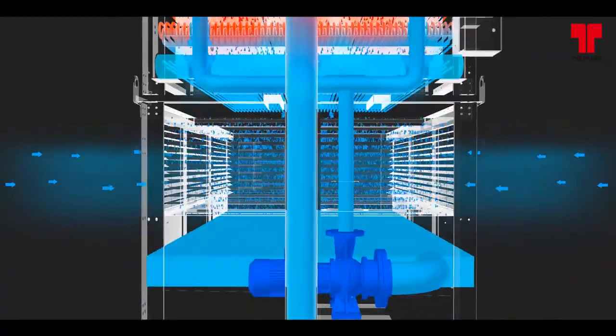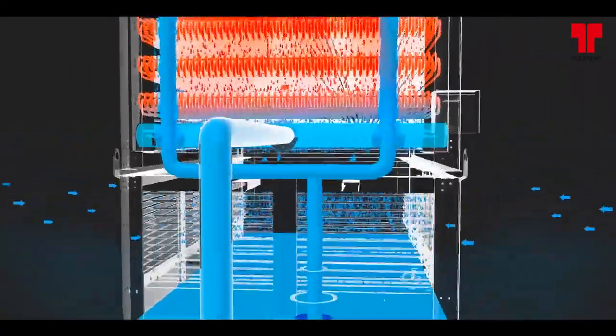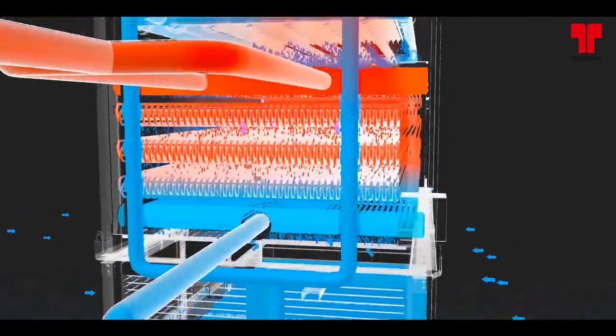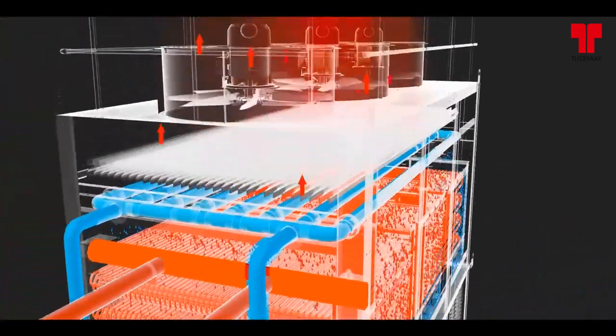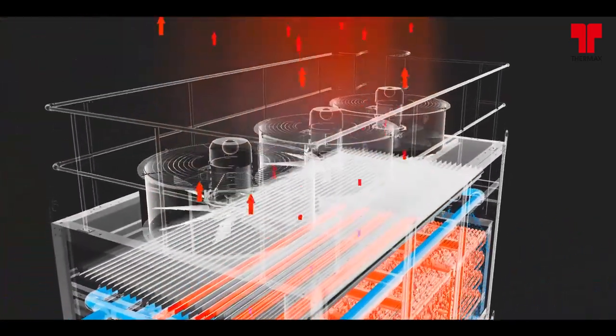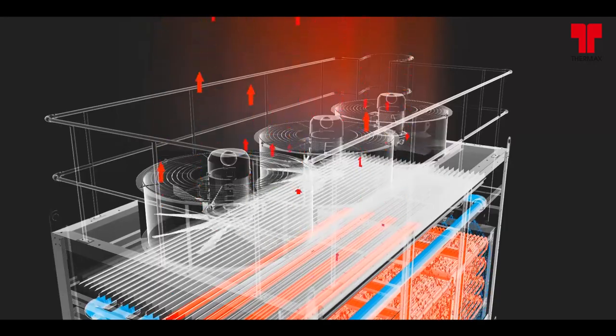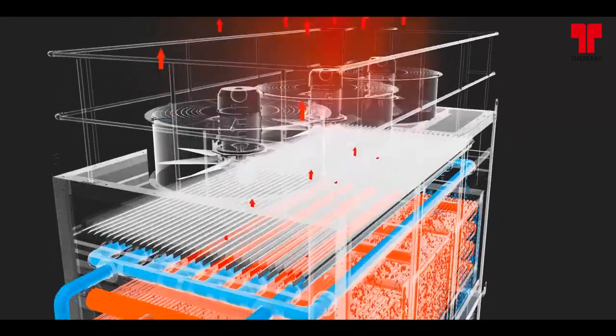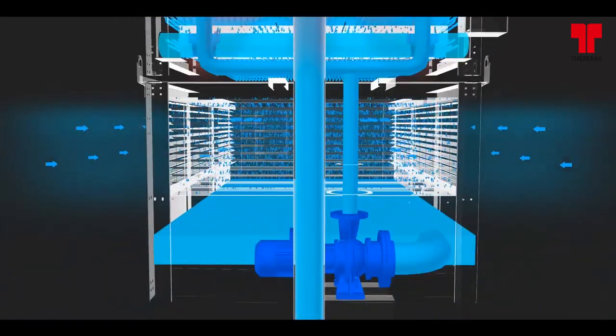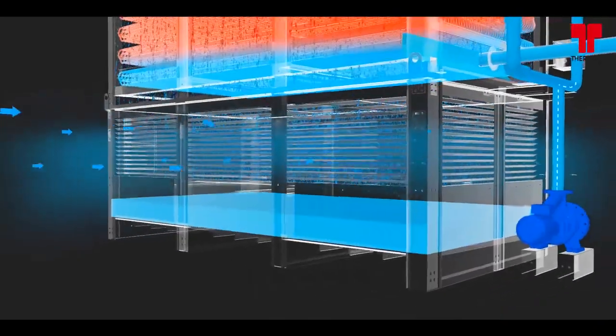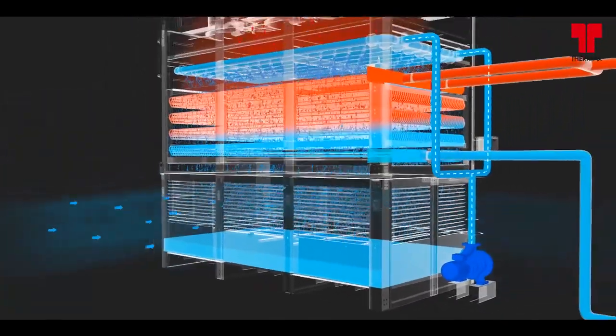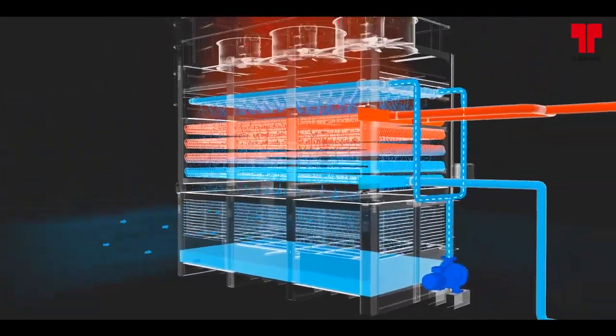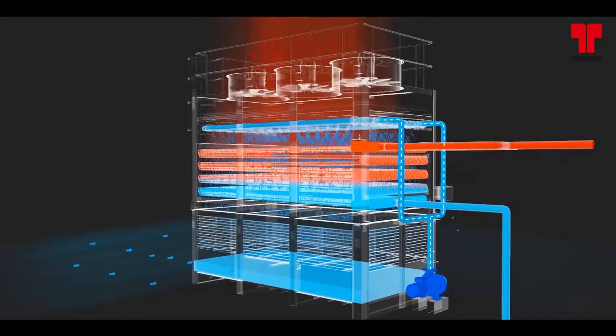The warm moist air is drawn by the fan and discharged into the atmosphere. The remaining cooled water falls to the sump at the bottom of the condenser, where it is recirculated by the pump up through the water distribution system and back down over the coils.